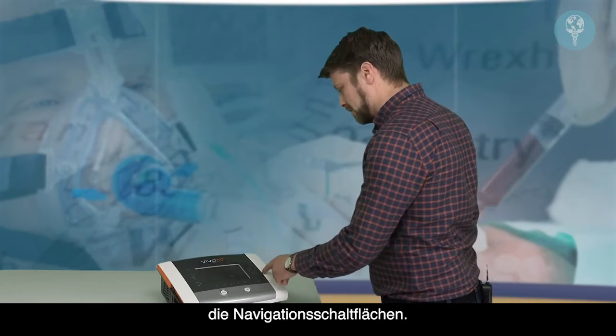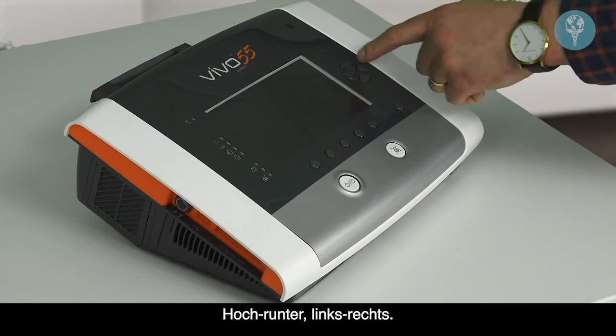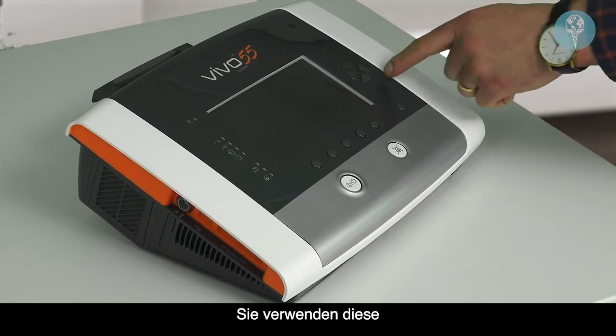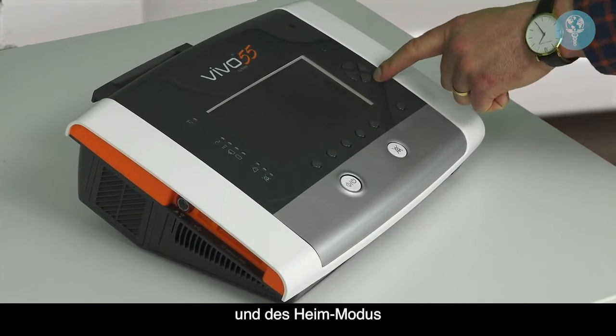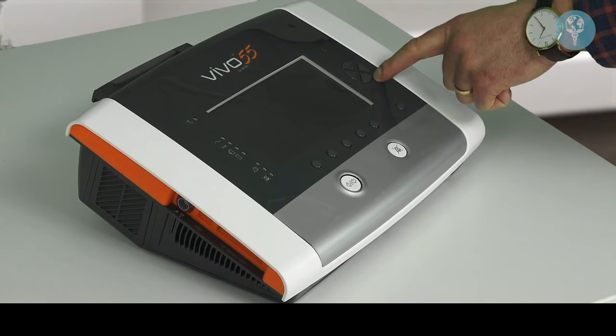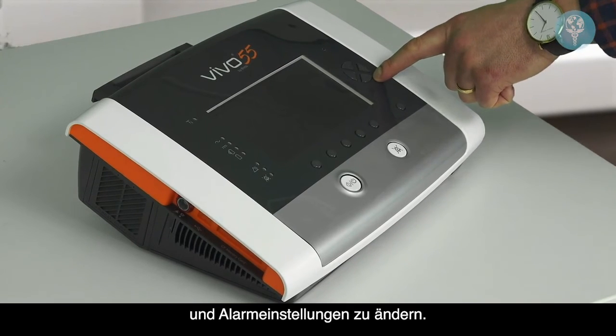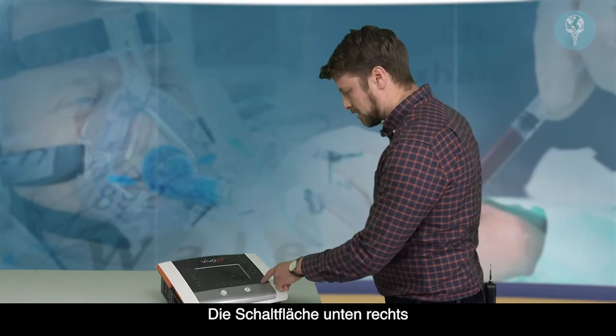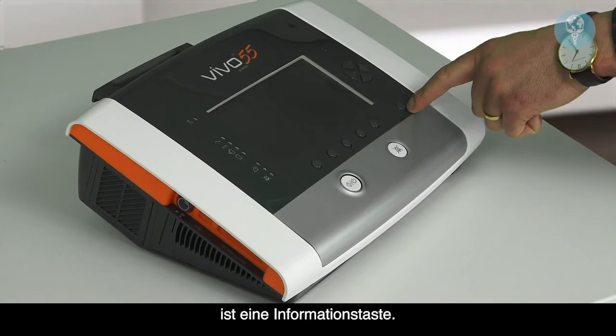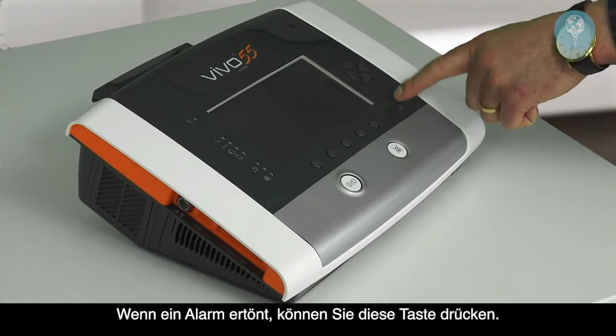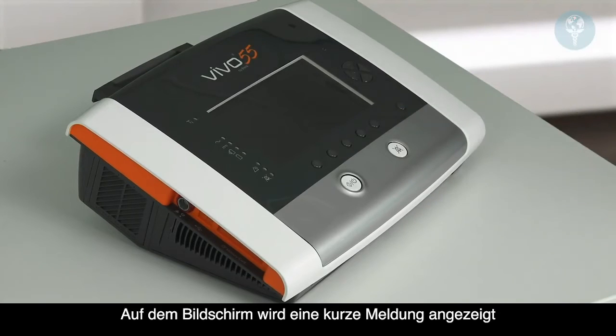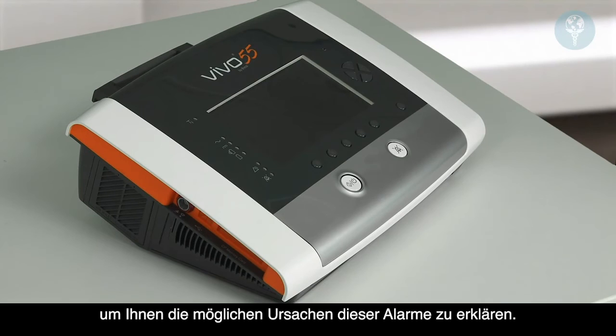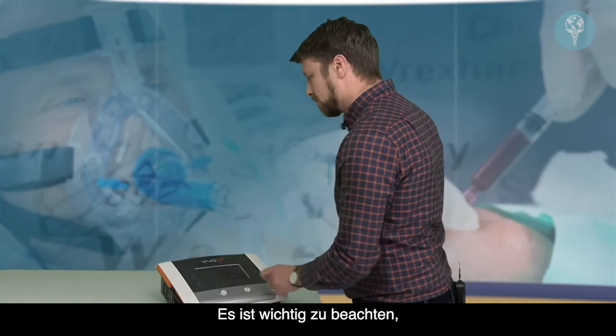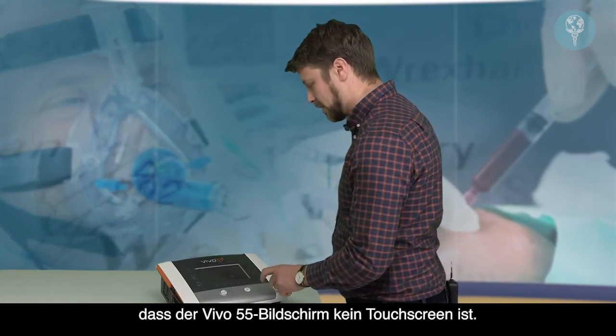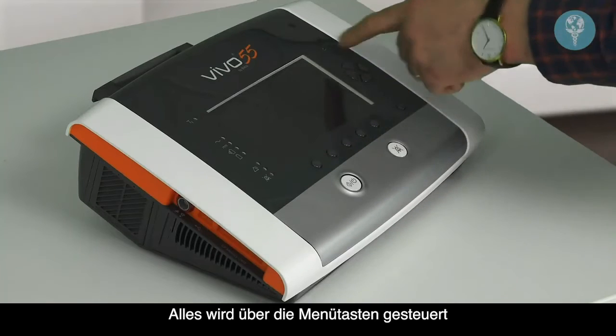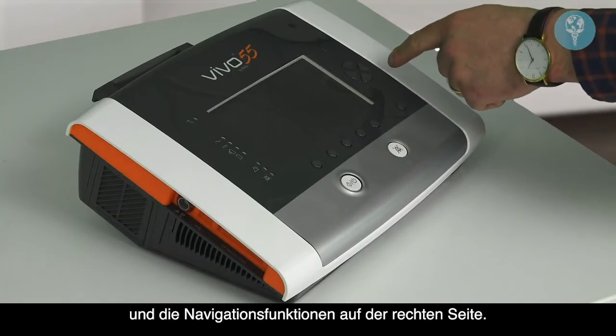We have on the right-hand side our navigation buttons, so our up, down, left, right functions. So you'll be using these to lock and unlock the clinical settings and the home mode, and also to change clinical parameters and alarm settings. The button on the bottom right here is your information button. So if any alarms are sounding, you can press this and a short message will appear on the screen to give you the potential causes of those alarms. Important to note, the Vivo 55 screen is not a touch screen. All of it is controlled via the menu buttons and the navigation functions on the right hand side.